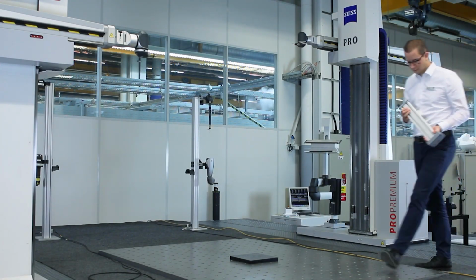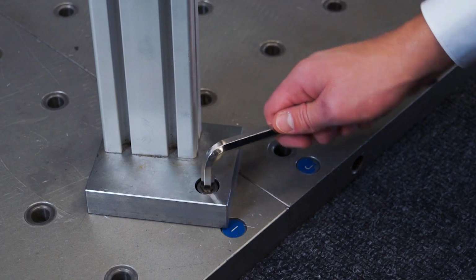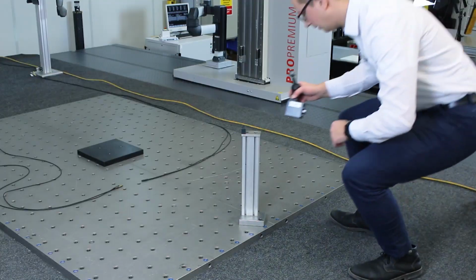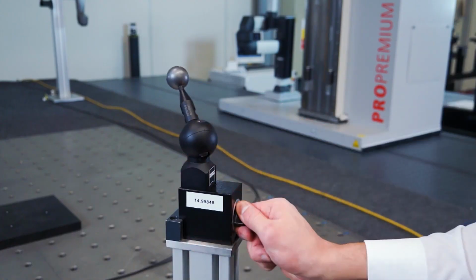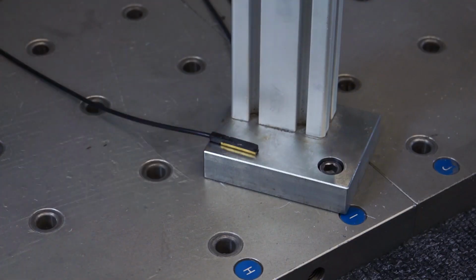We now switch to the machine and mount the reference sphere at the first position. The temperature sensors of the 2 columns must also be attached to the base of the sphere.